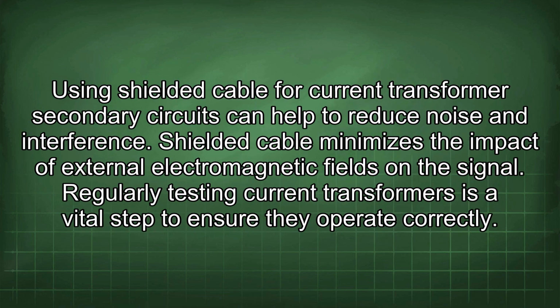Using shielded cable for current transformer secondary circuits can help to reduce noise and interference. Shielded cable minimizes the impact of external electromagnetic fields on the signal.